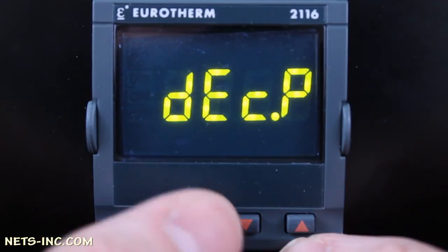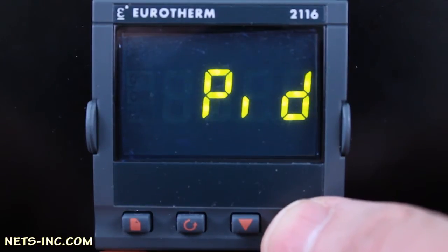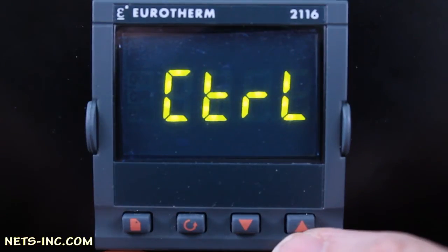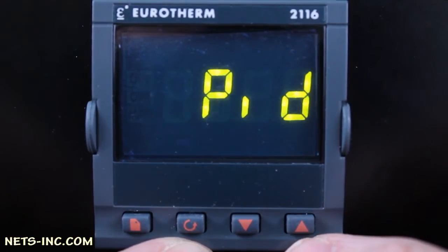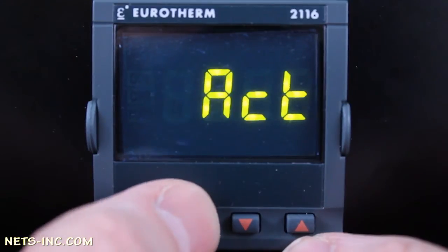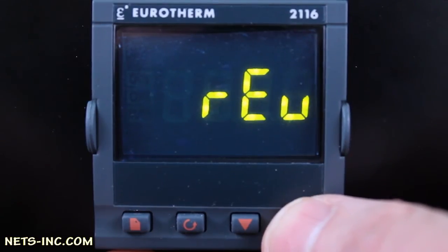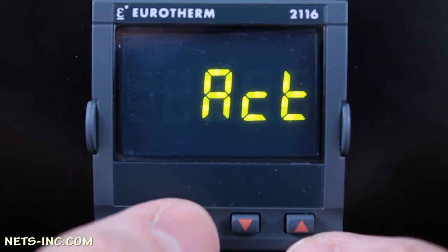Press the scroll key one more time to display CTRL. This is the control mode for the instrument. We want our instrument to be a PID controller. Press the up arrow and it is set for PID control. Pressing the up arrow continually shows you the other options other than PID. Press the scroll key one more time and ACT is displayed. This is the PID output action. For this type of control method, reverse action is the chosen method. Press the up arrow to confirm it is set for REV or reverse. Press the scroll button until INST is displayed.